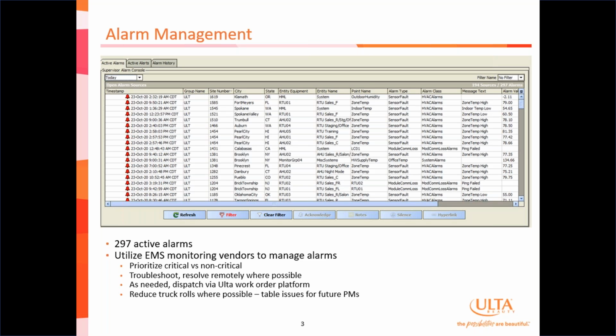I'd be completely inundated. So what we do is we utilize EMS monitoring vendors to manage alarms on our behalf. And they'll prioritize critical alarms versus non-critical. Is it something that's immediately impacting the store environment, or having a significant impact on energy consumption in the short term, versus something that may be non-critical, maybe an ancillary sensor that doesn't control anything, that's just for monitoring purposes, is in fault. That may not be as high of a priority. So we can prioritize issues that need to be addressed quickly.